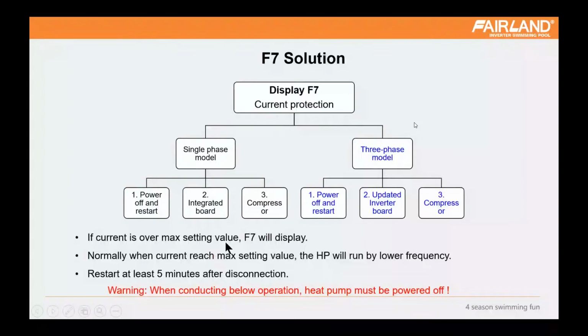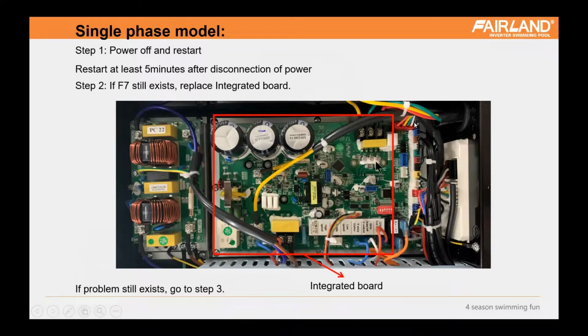Just like I introduced initially, if the DIP switch code is incorrect, then it will cause F7, the current protection, because the current is over the maximum setting value. Normally, when you reach the setting value, the heat pump will run at lower frequency. But if it fails, that means something is wrong. So F7 is also a protection, and we will ask the customer to power off and restart the unit. If that does not work, we will replace this integrated board.